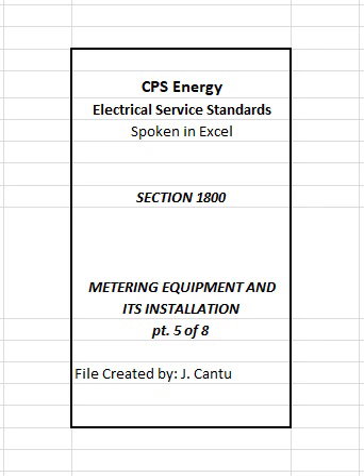1805.1. Prohibited locations. Metering equipment shall not be installed in locations specified below. 1. Areas that may be enclosed in the future such as patios, covered porches, and/or carports. 2. Areas subject to vibration, fumes, corrosive vapors, etc. 3. Over ramps or stairways. 4. Extending over driveways or pedestrian sidewalks, unless specifically protected from accidental contact or physical damage.